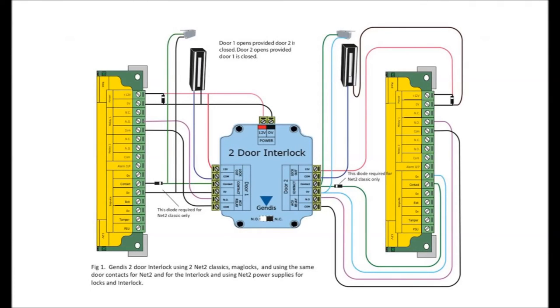You may wish to use monitored mag locks, and this is not a problem. You will need to connect from a normally closed, normally open or COM relay on the mag lock, and configure with the interlock such that the output is closed when the door is closed.